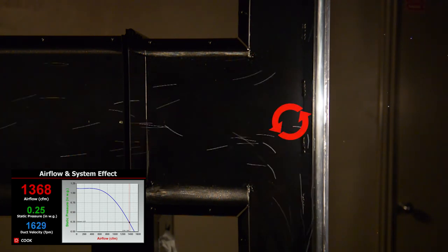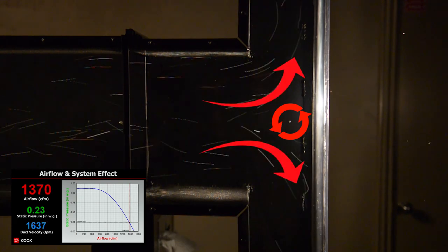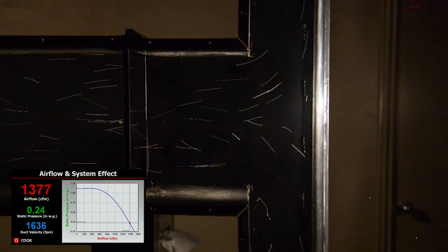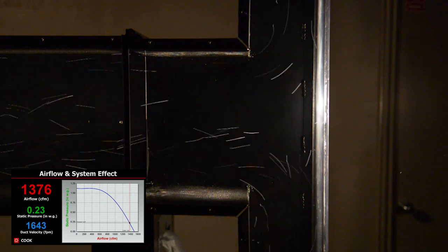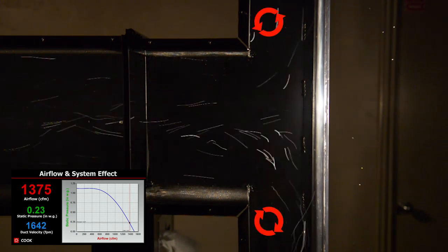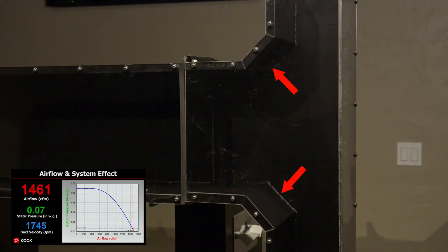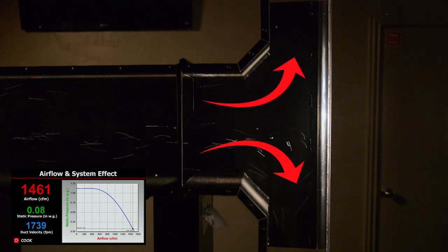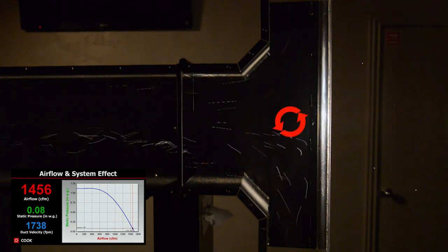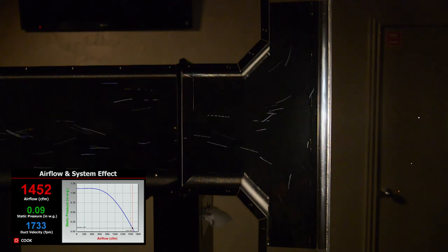Looking closer, we find that a small dam of air formed where the airflow splits, guiding the air to each branch. As we saw with the square elbow before, we are getting turbulence after the turn, contributing to the loss. Next, we have taken the bullhead tee and mitered the throat of the fitting. This opens up the throat area, providing more room for a smooth flow in each direction and minimizing the turbulence downstream. The pressure drop is similar to the square elbow with turning vanes or short radius elbow.